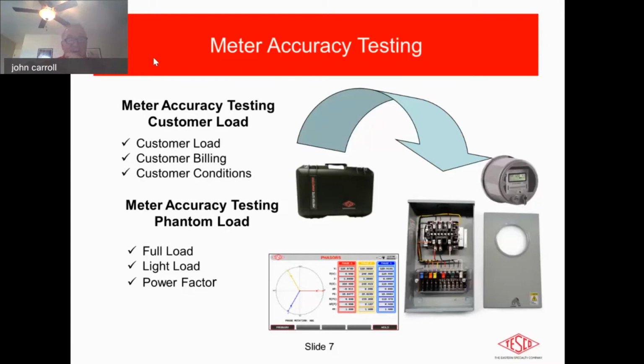So under a phantom load test, what we do is we shunt out the CTs themselves. We therefore bypass them, and then we drive current into the test blocks, which goes into the meter itself, and we can control that condition. Whilst that's terrific, it doesn't involve the CTs, but it gives you a test. It's particularly useful if you have a very low load condition on your customer. I'm thinking of an irrigation plant or a pumping station where there are seasonal conditions. Out of season, there's very little going on, so there's very little load. So this is a very significant and foolproof way of doing that test.